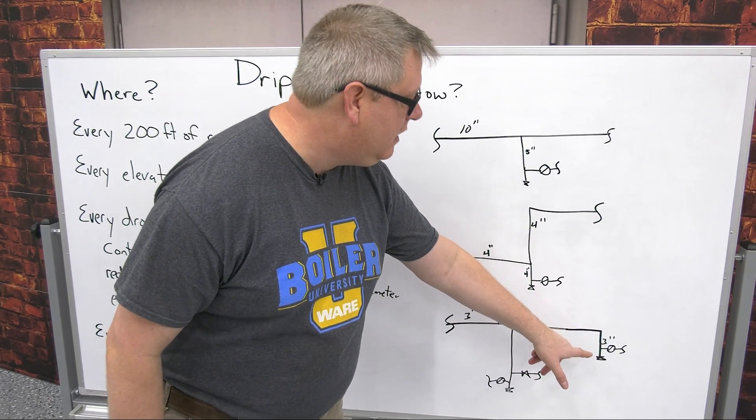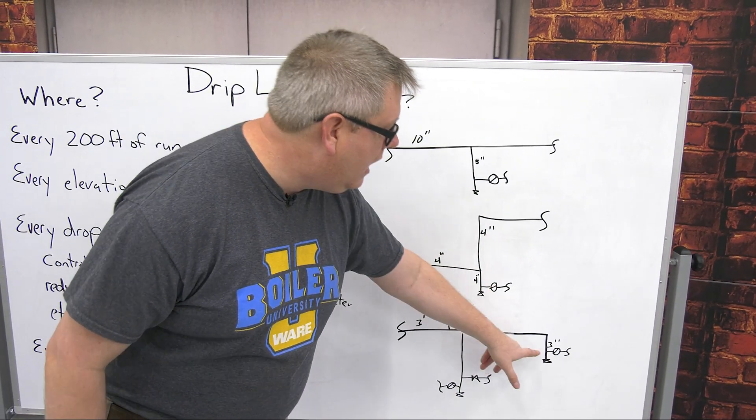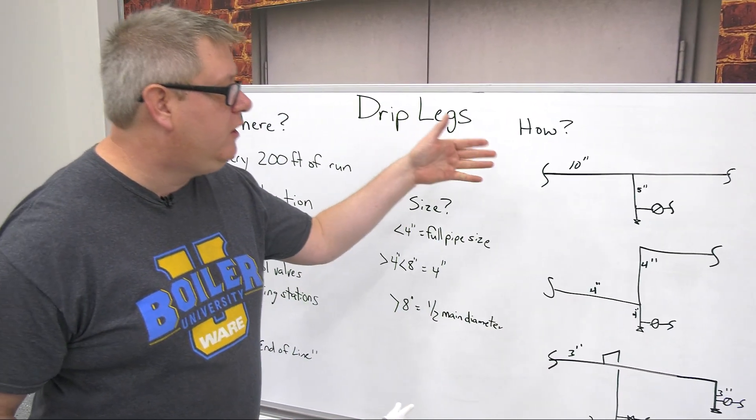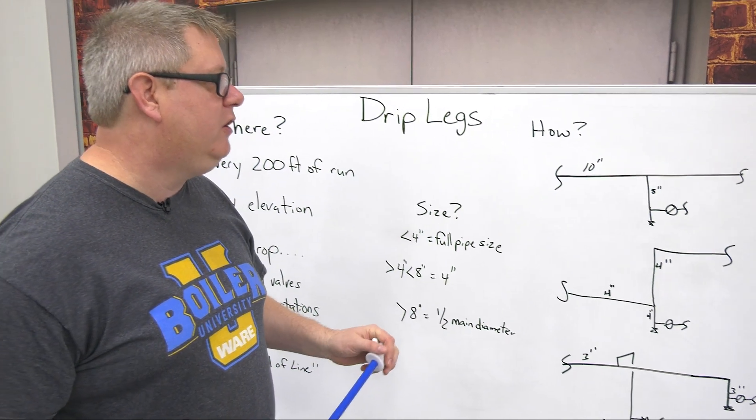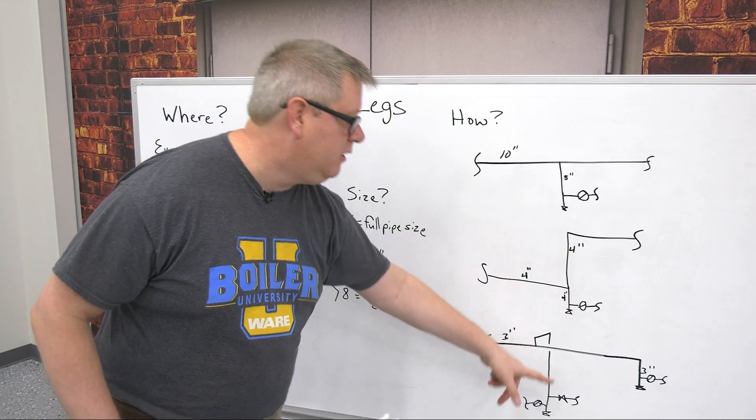So we'll drop with a 90 if we want to. We can use a T and put an air vent on there if we want. Come out the side to our trap. So those are different examples of how we would pipe those drip legs in. We've got a drip leg component and we've got a trap component.